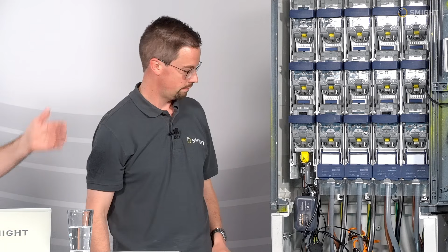You said gateway, so how is the connection between the sensor and the gateway we see at the door? As I said before, we have a Bluetooth connection. So the sensor here is collecting the measurement information from the cables directly, and this is sending via Bluetooth up to the gateway, and the gateway is sending that up into the cloud.